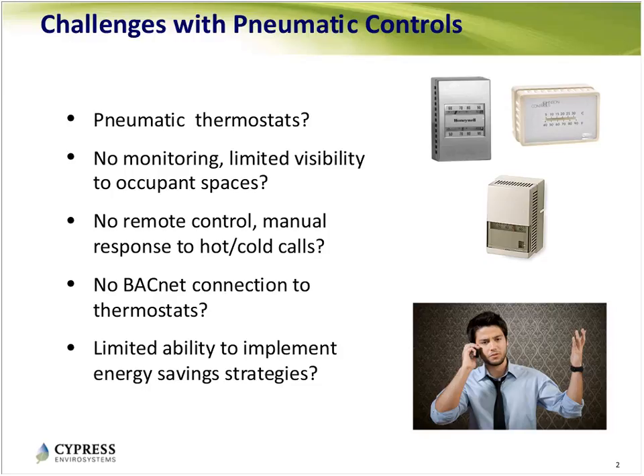Also, with pneumatic controls you don't get the remote ability to change set points. If someone is uncomfortable, or a space isn't being used - the office is empty - you can't just remotely dial in and change the thermostat to avoid heating or cooling. You have to physically walk up to the thermostat and turn the knob to change it, and then physically go back to change it again later. So it's very labor-intensive and disruptive, since you need to go into occupant space - which is really not done. That's another big shortcoming.